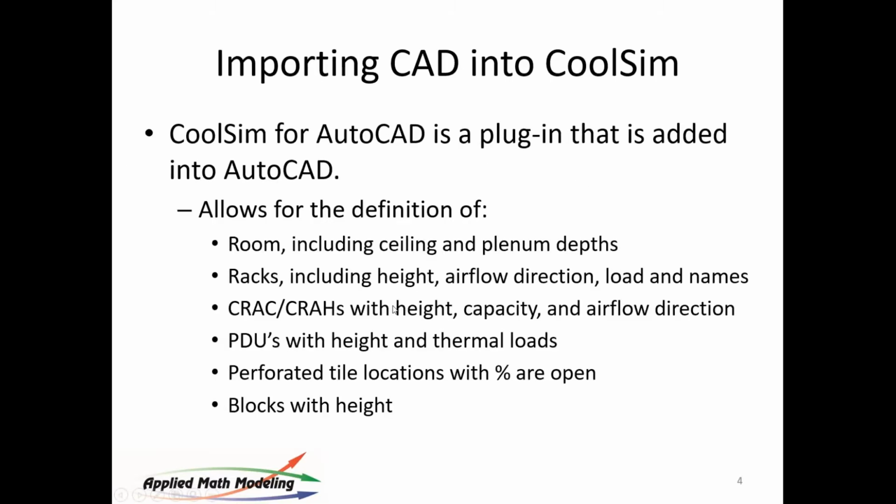So let's get started. The first thing I'm going to show you is importing CAD into CoolSim. This is quite important in a couple of areas. One, if you're a co-location provider, or you manage a data center that has other people's equipment in it that you're renting, or you're selling SLAs, you're selling capacity, then it is likely you've got a layout of that room in AutoCAD or Visio. And you often want to know what's going to happen if you add racks or you're going to sell an SLA to somebody. My best customers in the colo space will use CoolSim as a tool to ensure that the SLA agreement can be met.